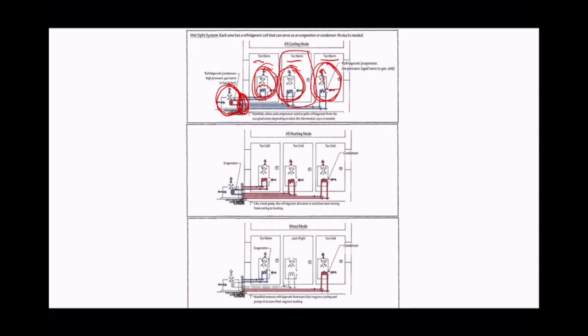In this case, we've reversed it, so it's a heat pump. We've made the low pressure cold part outside, which makes the high pressure inside, and we can provide heating to all three spaces. The benefit of this is that on a mixed day where we have east and west facing rooms, north and south facing rooms, or more commonly, but less thought of by architects, core rooms, which often need cooling in the winter, and perimeter rooms, which often need heating in the winter because they have skin area adjacent to the outside, so they have convective leaks coming in, and conductive heat loss through the skin itself.